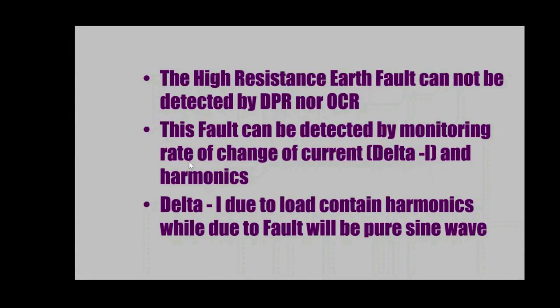This delta I is working on rate of change of current and harmonics. Why do harmonics come into the picture? We already saw an example. Whenever you start 6 motors in parallel, starting current is high. Whenever a train suddenly enters into a section, the amount of current withdrawn will be high. Therefore, how will you differentiate between a fault and the movement of a train? To do that, we use harmonics. So how does it work? You can see here the next line. When there is load, harmonics will be there. That is, when a locomotive is traveling, harmonics will be there. Whereas a fault will be a pure sine wave. This is the definition of RDSO.